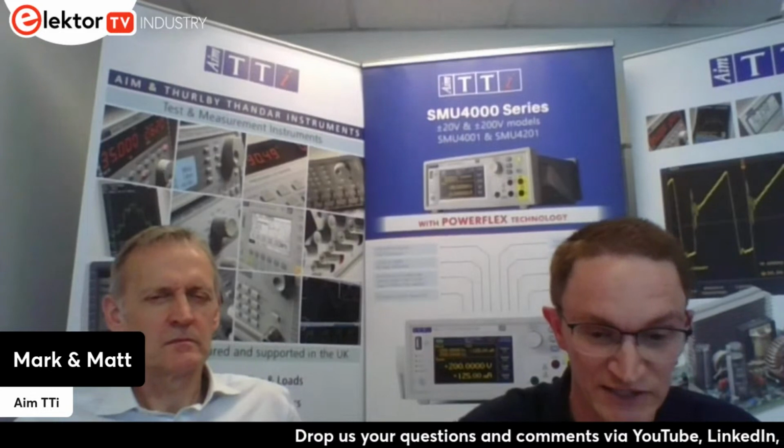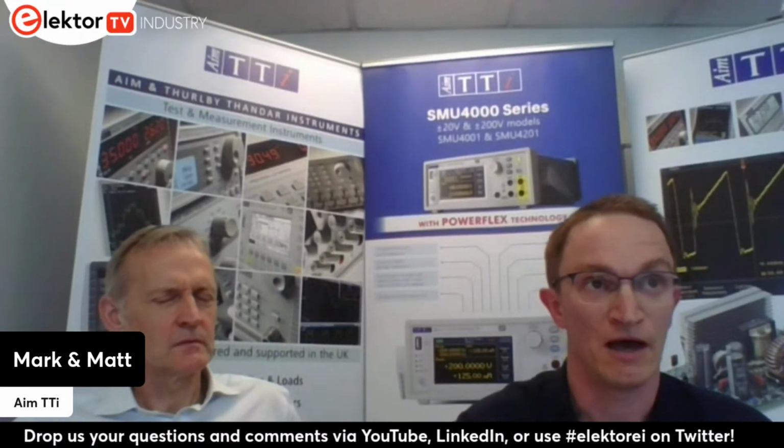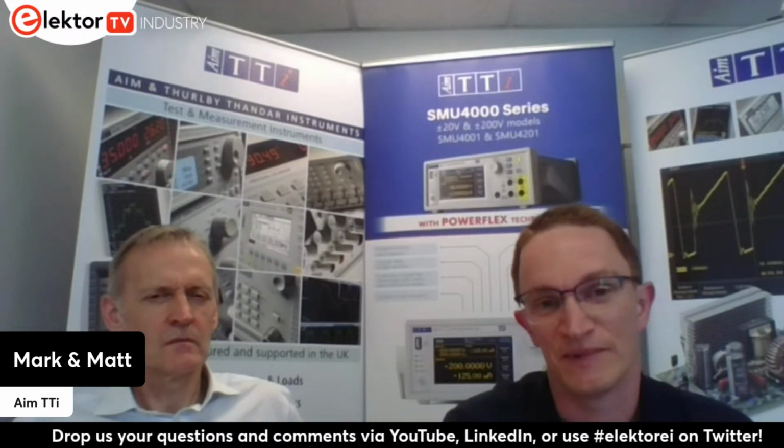One of the features we added, and a lot of people already have, is a measurement delay, so you delay the measurement until it's stable. But one thing we did with our auto version of that is to look at the measurements at a very fast rate, a rate beyond what the customer can see, to check when that source level has actually reached stability, and we can then give the first reading back.